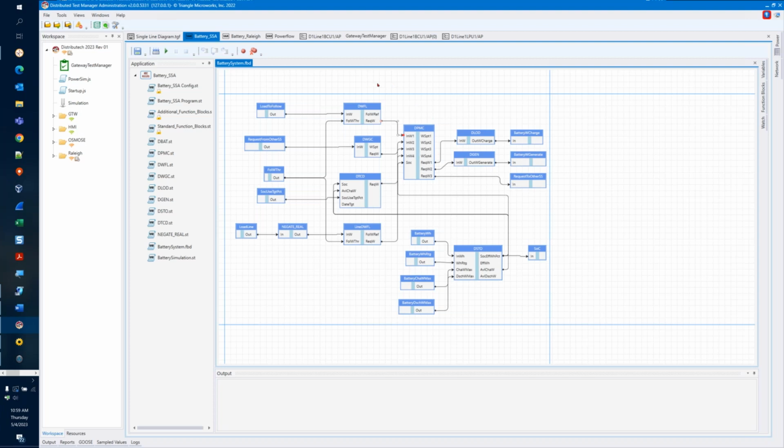Which brings me to source refs. So source refs also allow you to do things like this: specify connections between two logical devices before you really get to the communication side of things. You don't need to know or care whether or not these logical nodes will exist on different devices to specify a flow of data between them.